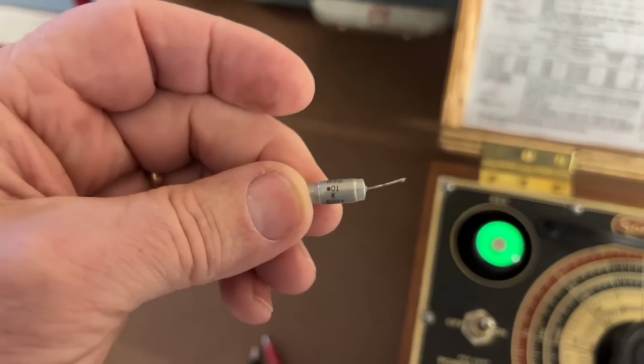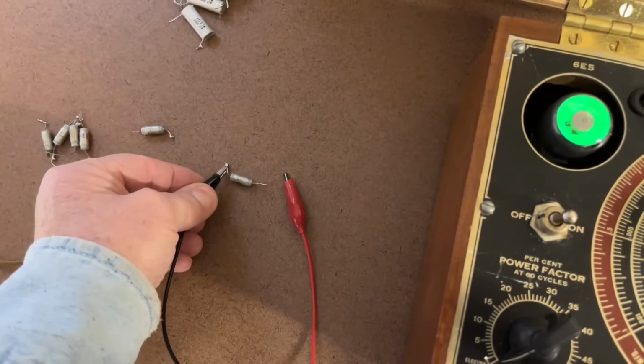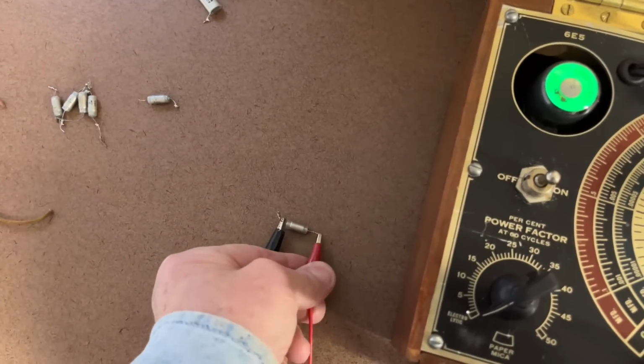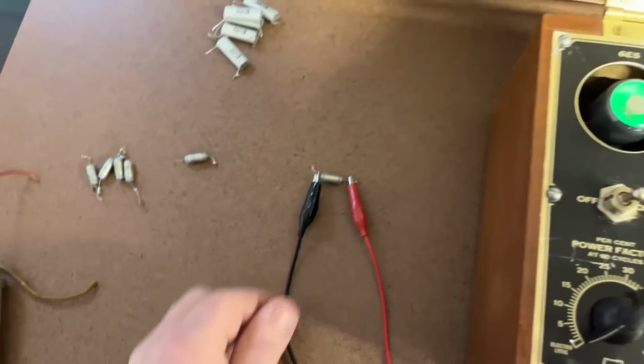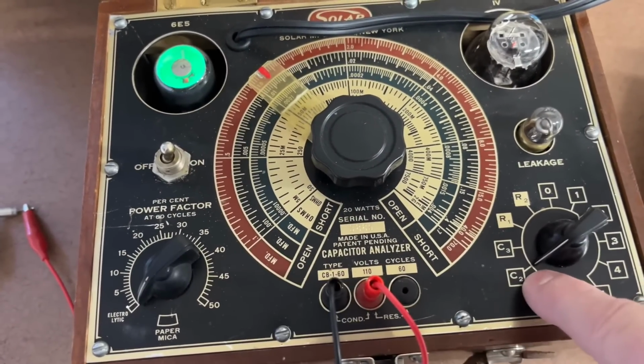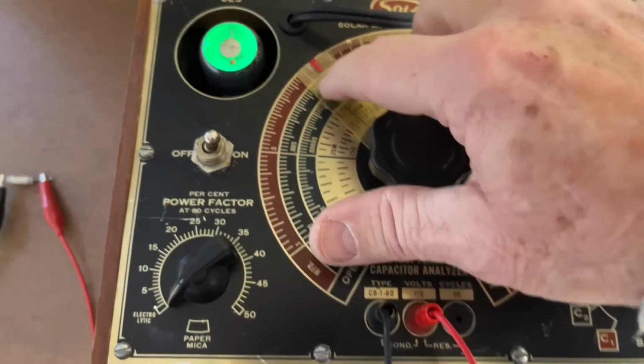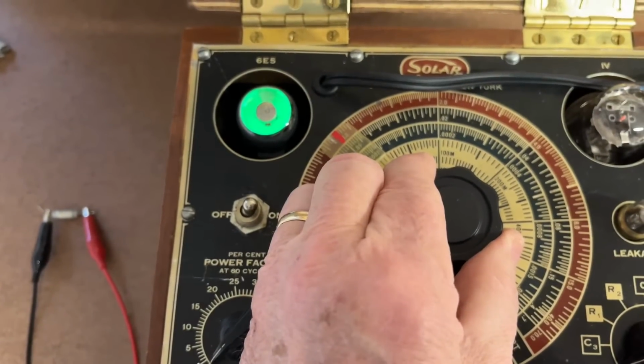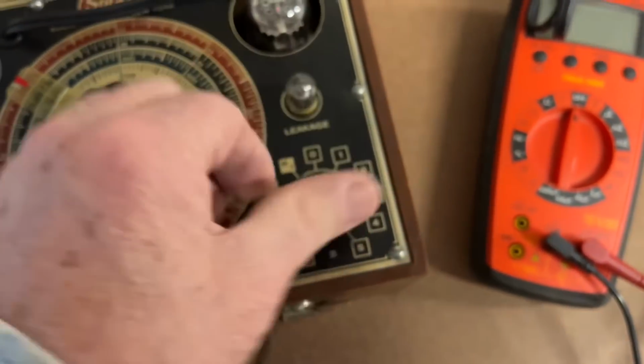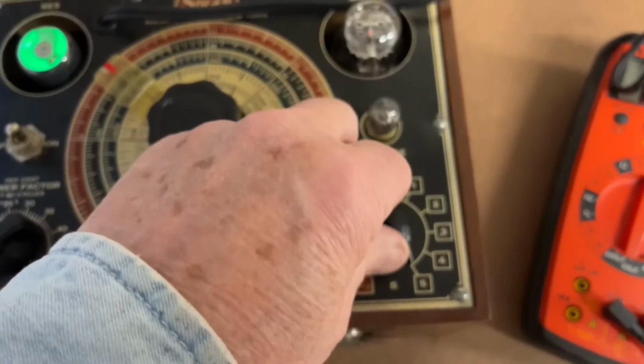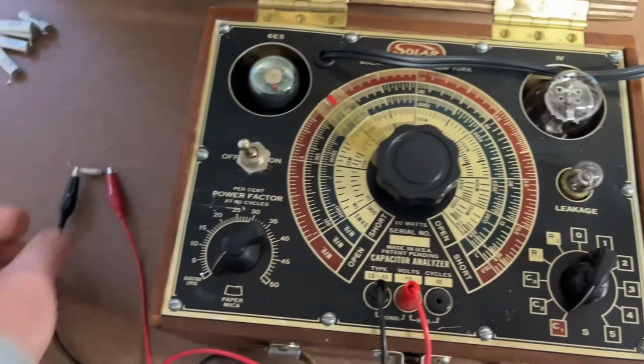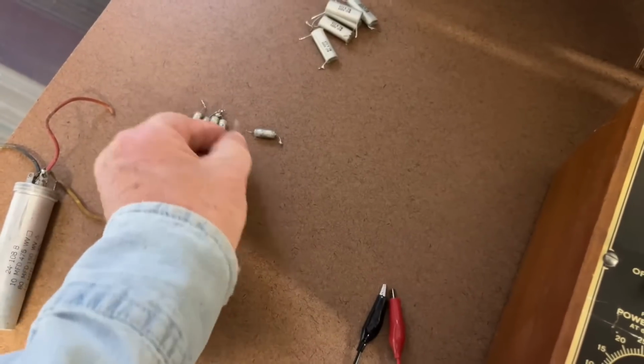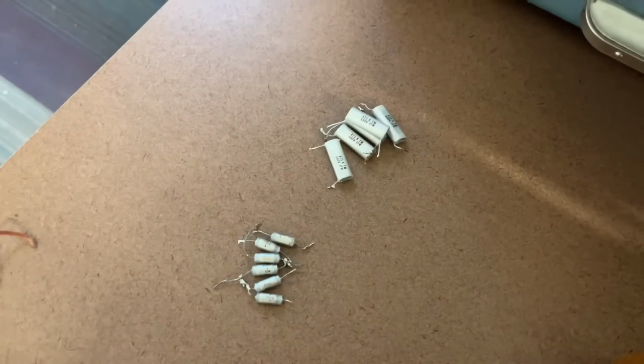These are 0.01s, I think. Yeah, 0.01. These are 600 volts. There are 4, 5, 6 of those. Second scale, C2. There's 0.01, and it checks right on it. Now let's go to leakage. 100, 200, 300, 400, 500, no leakage. As I suspected, all of these caps were good, but I'm still okay with changing them all.